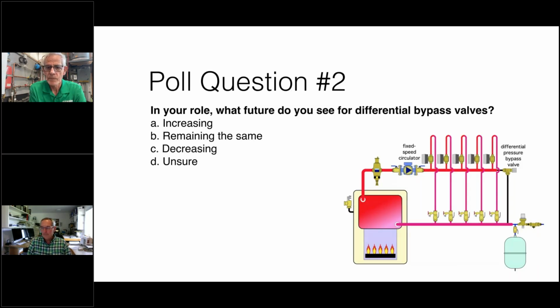And Siggy and I talked a little bit about how, with heat pumps, there might be a new market for a valve like this. What's happening with some of these heat pumps is the pump starts up before there's flow going through the system, so now you need a bypass or an escape route for that flow. Some people are building it into the systems, you said, Enertech or something. They are. In fact, we have a schematic coming up here if we have time for it. If we don't, it's going to be in idronics number 36, where these differential bypass valves are actually being used. So a heat pump can recirculate the flow until the temperature of the flow comes up to some preset value, and then a valve would open and the differential bypass valve would close. That is a very different application from what I'm showing on the schematic, but it is definitely a current and likely a future application.